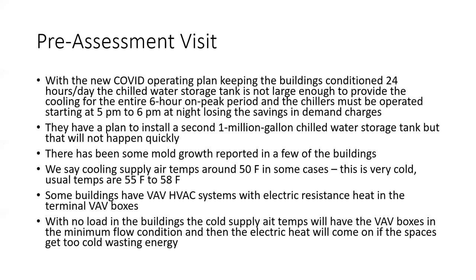And we've asked for copies of HVAC design prints, sheets, which they have digitally, but they've not sent us any yet. Because the only way you would know would be to check the design and see if this was really designed around 50-degree supply air temperatures, which I tend to doubt pretty severely, but I don't know until I see the prints. So we'll see.